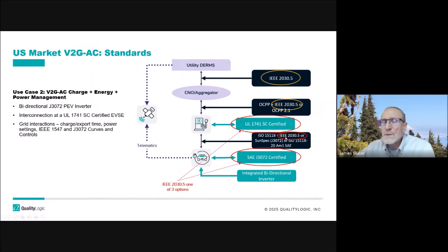Today, J3072 specifies - you saw the matrix that Steve put up - it has a matrix, but the only one that's really being developed at this point is IEEE 2030.5. That's what we're doing with the J3072 profile working group, and that's what we're using in the standards today. In the future, there's something called 15118-20 Amendment 1, the SAE version, a North American version, that will be released and can do the grid code management of these EVs. So that's important to note.